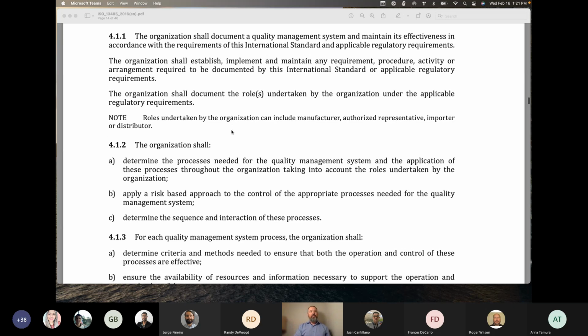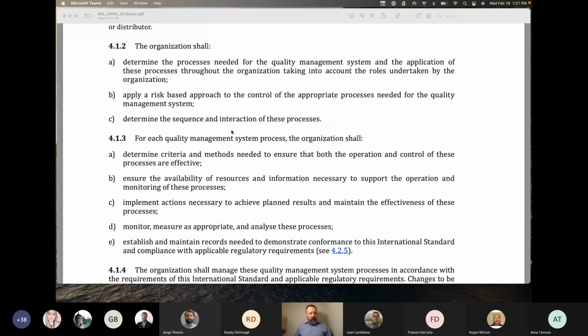Okay. As we move into section 4.1.2, the organization shall determine the processes that are needed by the quality management system based on the role that your organization functions. So you have to go through the standard and decide for your organization which clauses you have to comply with, and then have justifications for the ones that you do not comply with. You should apply a risk-based approach to the control of those processes. Hopefully, the phrase risk-based approach is one that is very familiar to you. And if you've heard myself or other site quality leaders say that we're going to take a risk-based approach to how we handle various problems within the organization, especially as we're moving things through the quality management system, there is a direct requirement in the ISO standard that says you should be using a risk-based approach in that decision-making process.